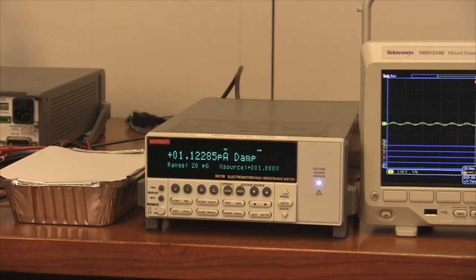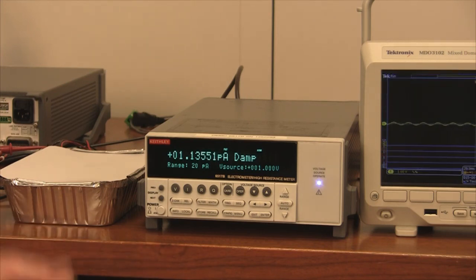Okay, in summary, how do you make proper low current, high resistance measurements? There are several factors. One, you have to have an electrometer or ammeter with extreme sensitivity, model 6517B. Use shielding as much as possible. The lower you go in current, or the higher in resistance, the more shielding plays a part here. Don't move the cables. If you move the cables, even with low noise triax cables, some amount of current will be generated. It's called triboelectric effect. Use Teflon insulation wherever you can to keep the resistance you're trying to measure isolated. All of the above will help you make proper low current measurements.